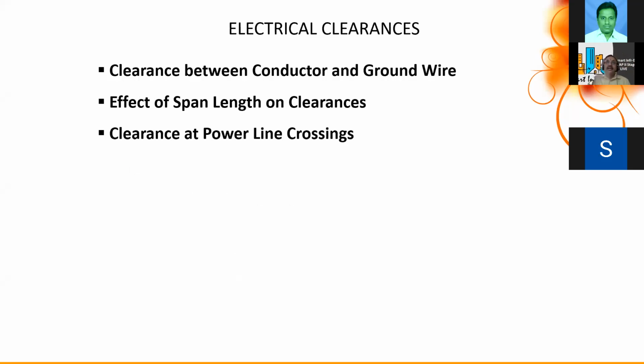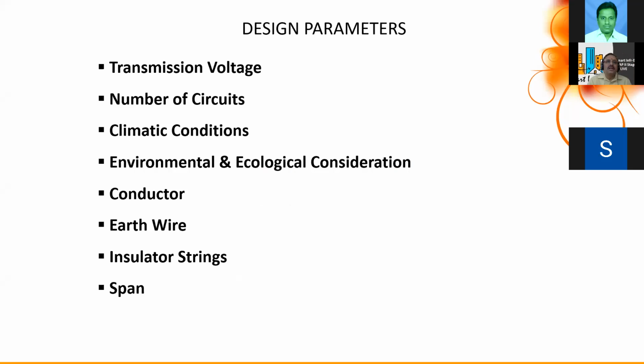So clearance between conductor and ground wire is also very important. That will determine the peak height. I'll show you all in the drawings probably. So voltage, number of circuits, climatic conditions, conductor, earth wire. Earth wire is for earthing, shielding the conductors from the lightning, and a span.